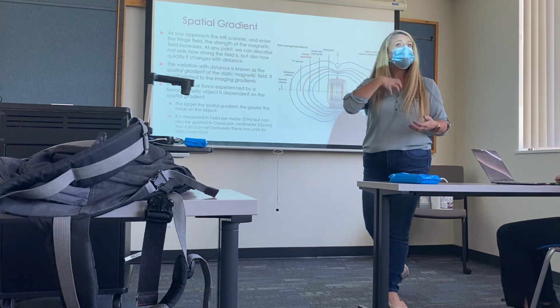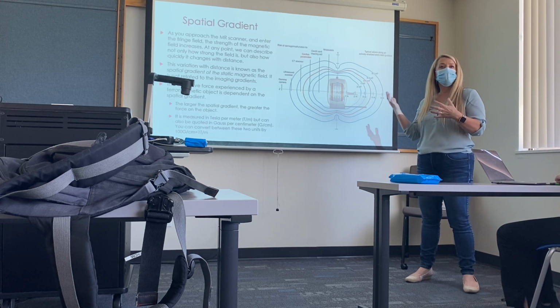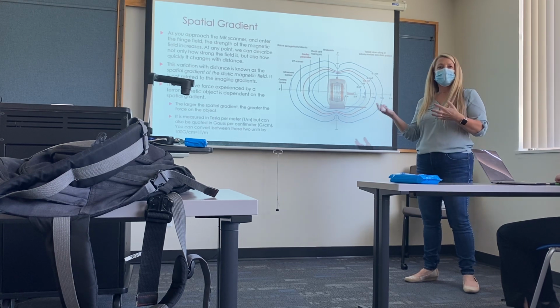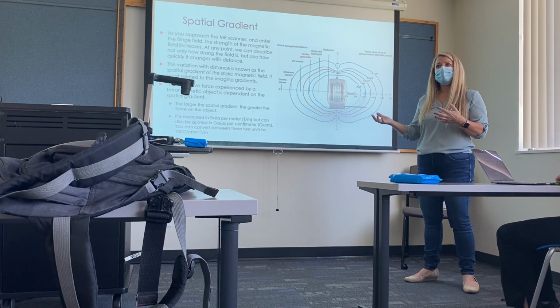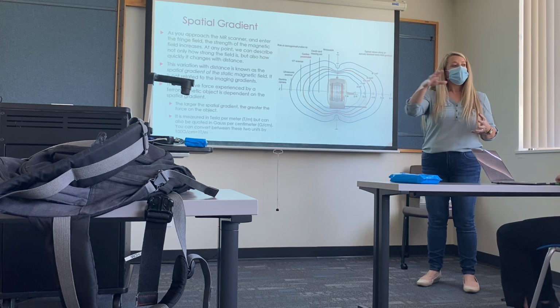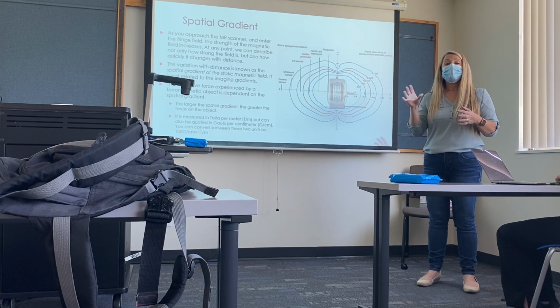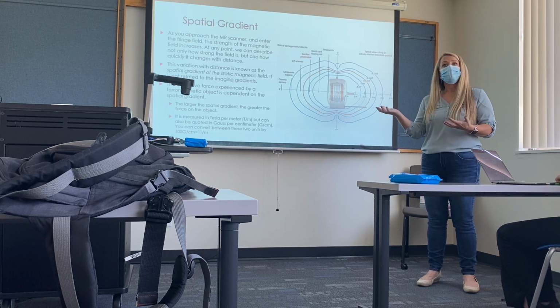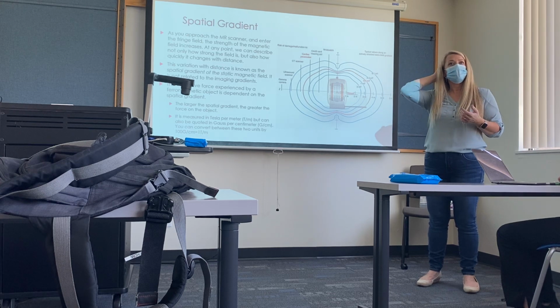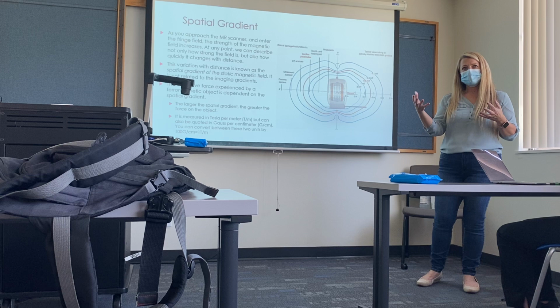Because certain implanted devices can stand up to a spatial gradient of say 0.7 Tesla, but not 0.73 Tesla. And so if you have, say, a little 0.5 system, there might be somewhere, because we know there's hot spots and cold spots, right? There might be somewhere where they would experience that high of a spatial gradient, where in space this particular strength magnetic field is, and so they can't go in the room, if that makes sense.